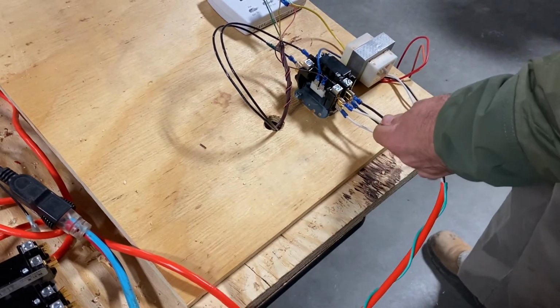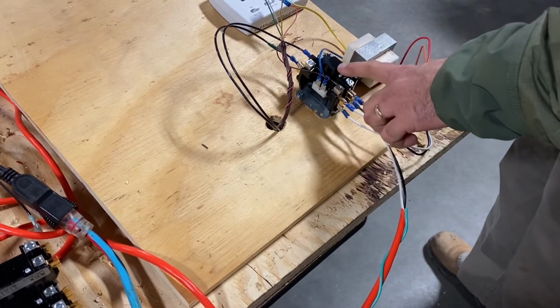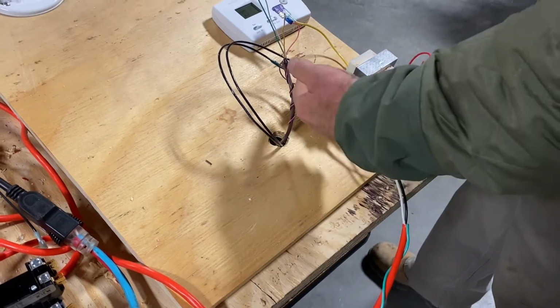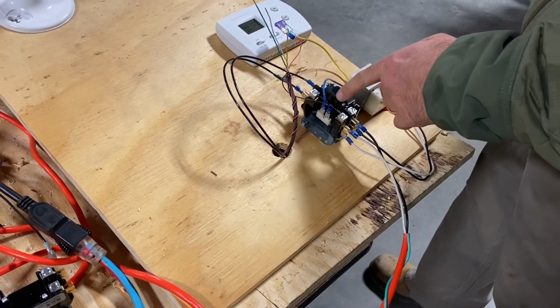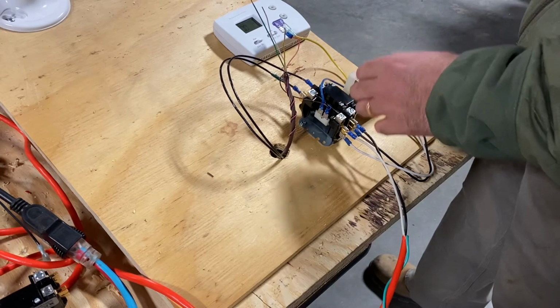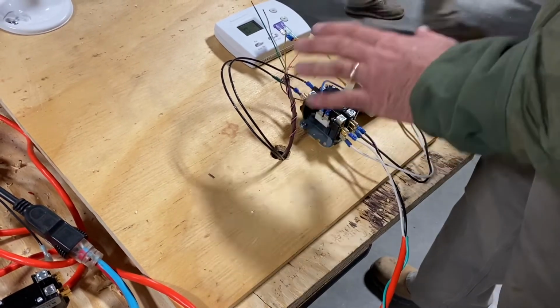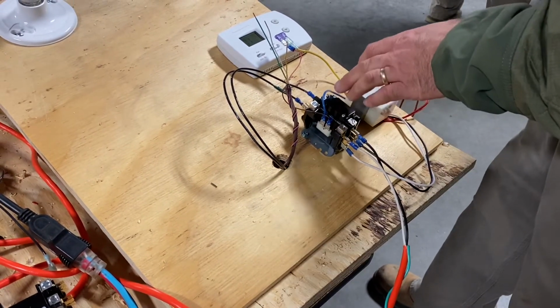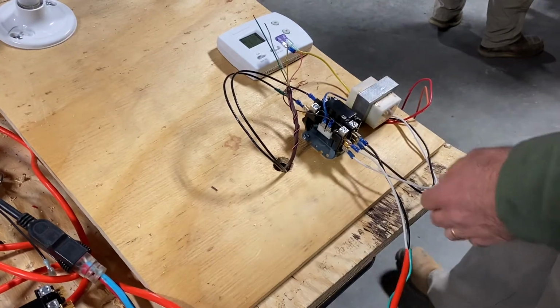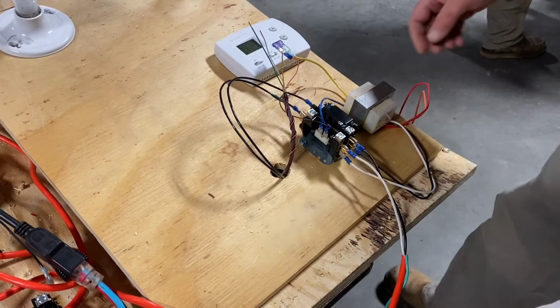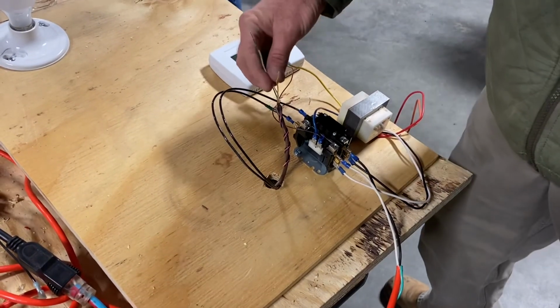We've got L1 and L2 connected to a single pole contactor. That means that this side is - you can actually see it's one solid piece of metal there - so it's on all the time. This side is switched, so it opens and closes, and we're going to open and close that with low voltage from our thermostat.